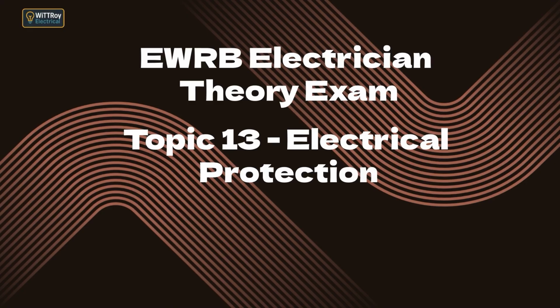A semi-enclosed rewirable fuse uses fuse wire that melts under overcurrent, simple but coarse protection. HRC fuses are sealed with a calibrated element and sand filler, giving fast and safe interruption at very high fault currents. MCBs use thermal and magnetic mechanisms to trip on overloads and short circuits and can be reset. Cartridge fuses are sealed one-time fuses used in appliances or control gear.